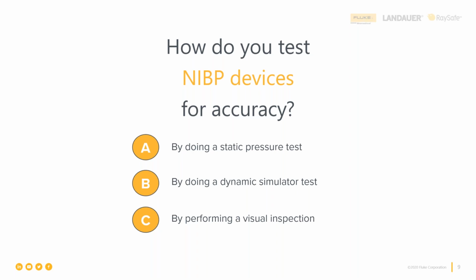Well, so what about the other two? You should be performing a visual inspection every time that you periodically go and test the patient monitor, the NIBP device. You're going to do some leak tests on the cuff and the hose. You want to make sure that visually things are looking okay. That's fine. But again, that's not about accuracy of the NIBP device. It's about making sure the device is actually going to function properly to begin with. You have to do that before you do your accuracy assessment.